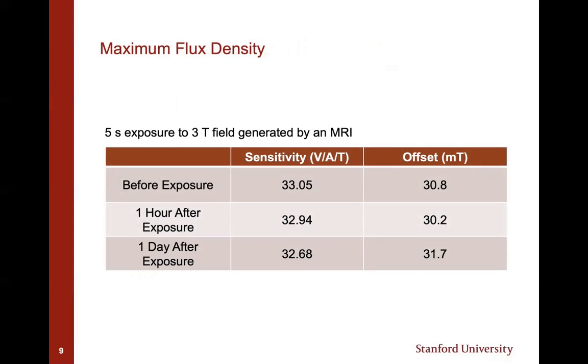Now, after mounting these sensors to STBs, we needed to see if their sensitivity or offset was permanently or even temporarily affected after being exposed to an extremely high magnetic flux. Prolec GE suggested that a short in one of their transformers could generate a 2.5 Tesla field for 3 seconds. So we exposed our sensors to a 3 Tesla field for 5 seconds by placing them in an MRI's B0 field. Now here you're seeing current bias sensitivity, which accounts for the current we fed the Hall sensors. We measured sensitivity using a Helmholtz coil set up in our lab. Sensitivity and offset, as we can see here, had no major changes, and the small variations we do see fall within the bounds of experimental error.